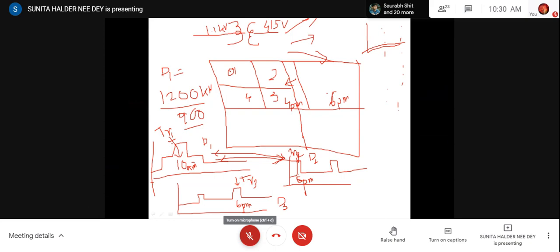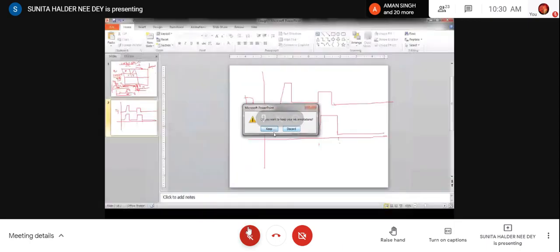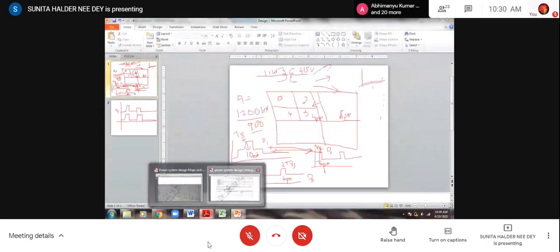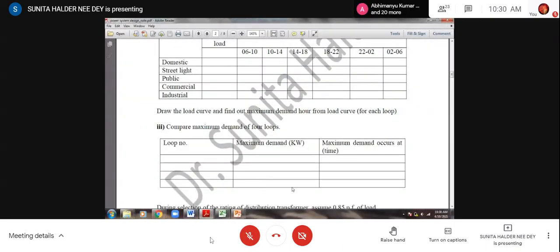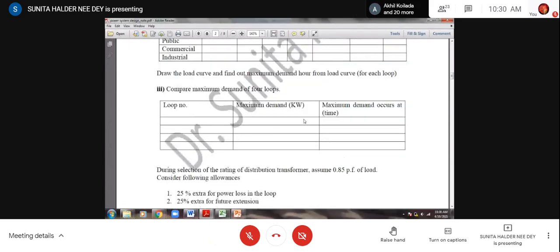Have you understood my point? It may not be required because in your case residential loads are dominating, but this check is very much required. Otherwise the transformer size will come out different. So if you check that, it will be reflected in this table 3.